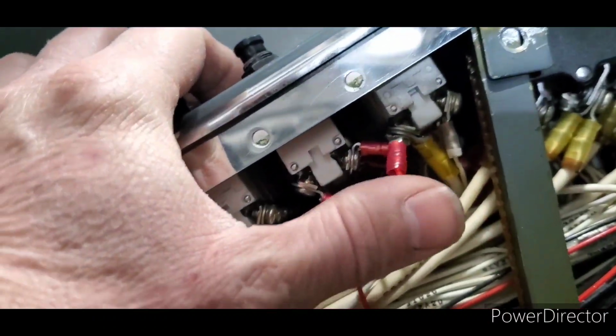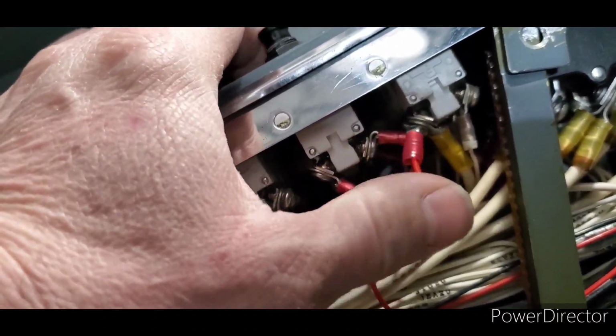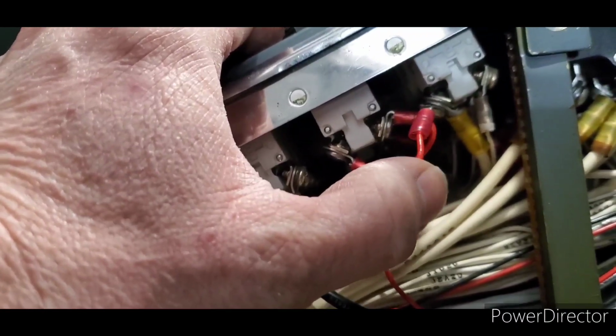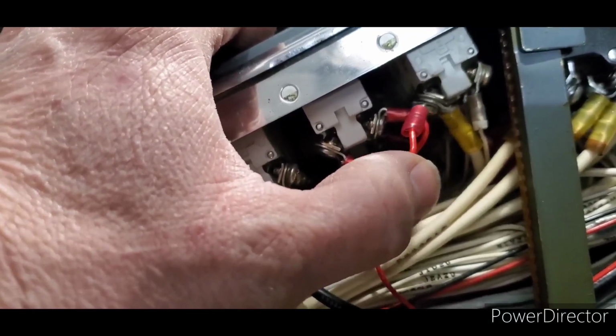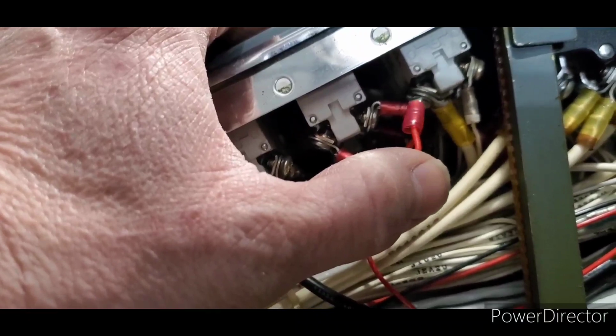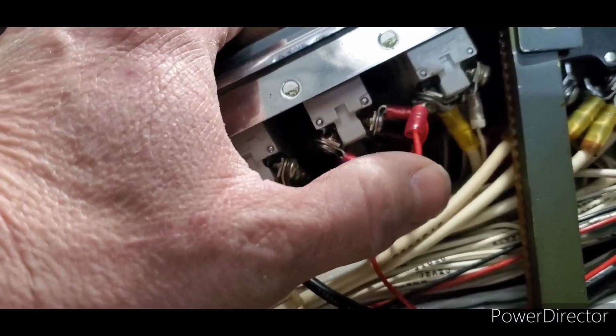Because, oh, look at that. That will cause arcing, could cause heating up, could cause the terminal to arc through the wire, and an intermittent fault that you'll have to troubleshoot.